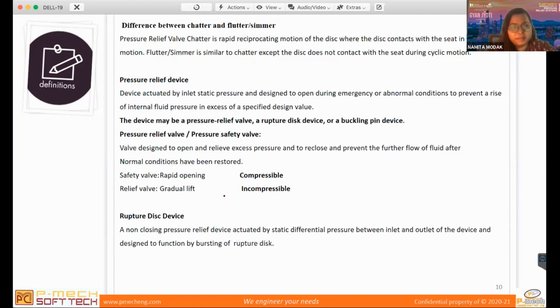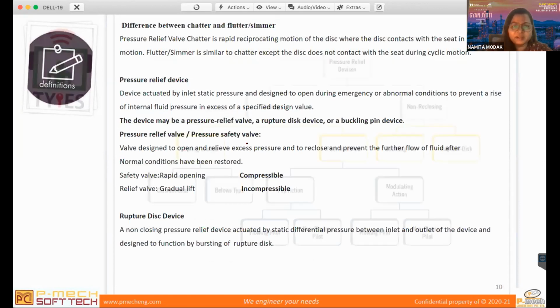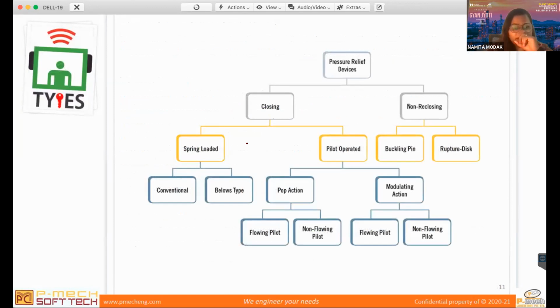So along with the pressure safety valve, there is another device called the rupture disc. I will show you a table where you can get a good idea about it, that these pressure relief devices are categorized as reclosing and non-reclosing. So basically reclosing is like in the case of a PSV, once it has popped, it will close to its original position. But in non-reclosing, once it pops, it gets broken, so you have to replace that device.